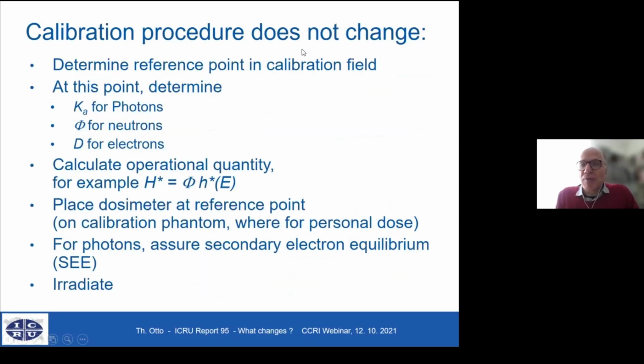Now, the good news for people involved in calibration is that the calibration procedure doesn't change. It is still the same song. You determine the reference point in a calibration field. At this point, one determines with suitable primary detectors or secondary standards the air kerma for photons, the fluence for neutrons, or the absorbed dose for electrons. Then one calculates the operational quantity by multiplying the field quantity with the conversion coefficient, as given here. And you place the dosimeter at the reference point, and don't forget to put a calibration phantom if it's a personal dosimeter to give the necessary backscattering effect of the trunk.